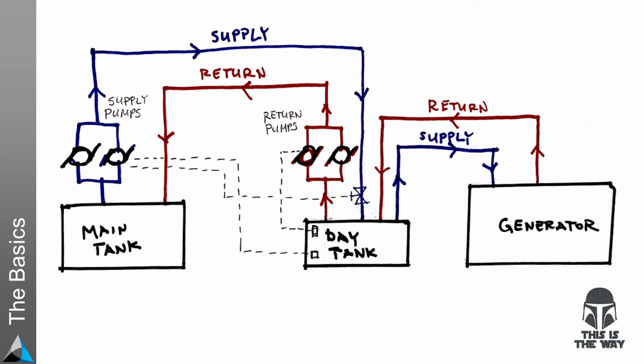There's a main tank that has fuel in it. Supply pumps usually feed the day tank, then from the day tank over to the generator, and return lines back to the day tank, with return pumps that pump fuel back from the day tank to the main tank. There's a lot more detail, with float switches and solenoid valves, some of which I've tried to show, and depending on how the system is arranged and configured, it might look a little different. But that's the fundamental building blocks of the system I'll be talking about regarding supply pumps and return pumps.